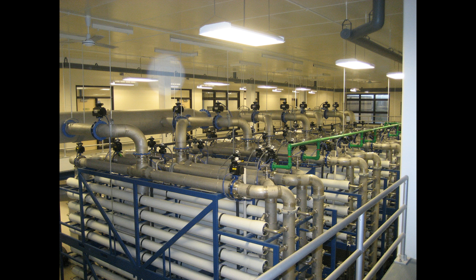The plant's filtration system is nearing the end of its effective lifespan and is needing to be repaired more frequently as a result. Repairs are needed on the filtration membranes one to two times a month.